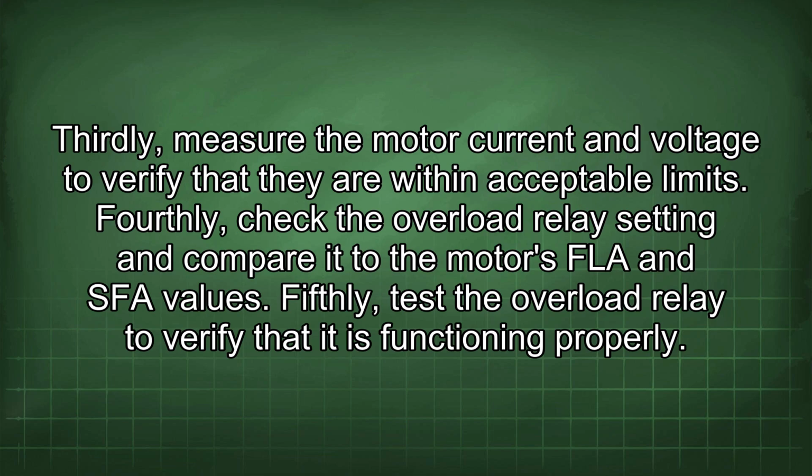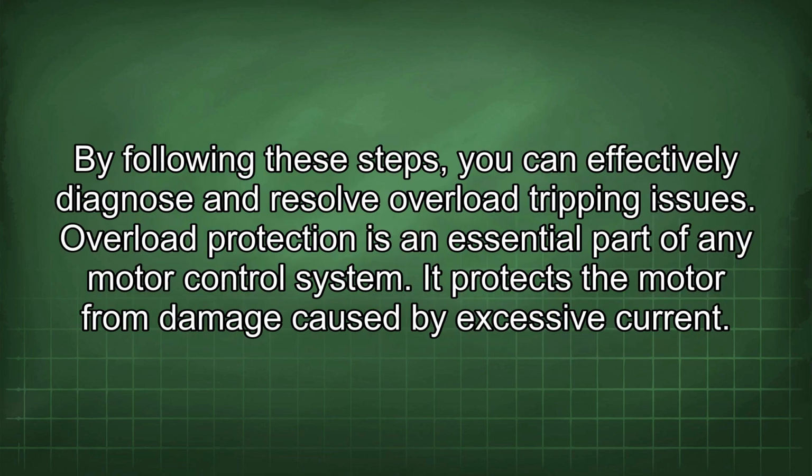Fourthly, check the overload relay setting and compare it to the motor's FLA and SFA values. Fifthly, test the overload relay to verify that it is functioning properly. By following these steps, you can effectively diagnose and resolve overload tripping issues.